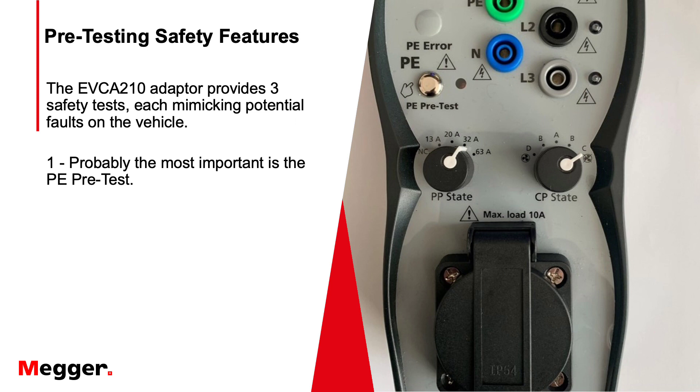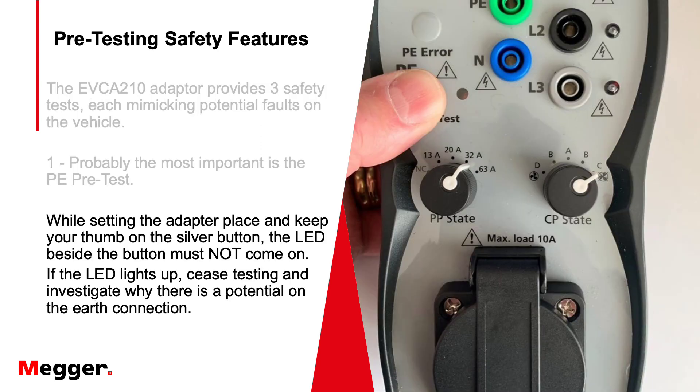The PE pre-test is probably the most important one of all — it makes sure there's no potential on the earth. You simply put your thumb on the silver button and check all conditions and all charge states while setting up. If the LED light to the side of the button does light up, you should stop all testing and find out why there is potential on the earth and what value it is, because you're allowed up to 50 volts but you don't want anything higher on two tons of steel insulated on rubber tyres.